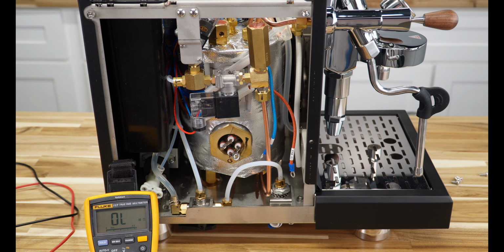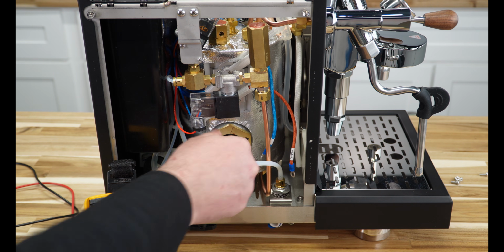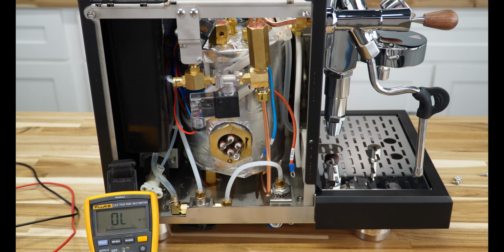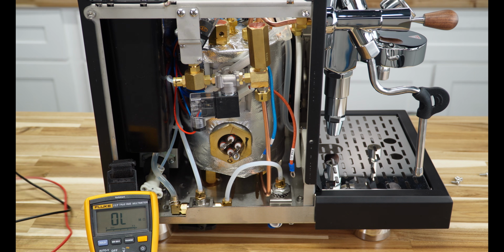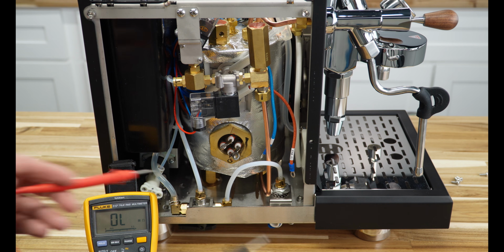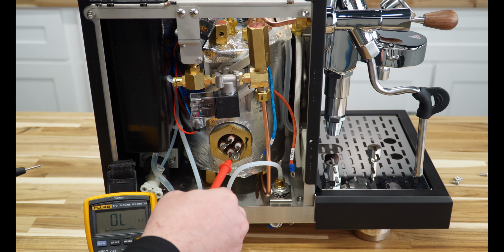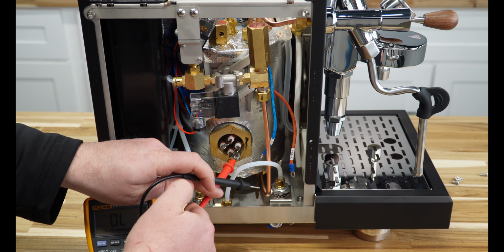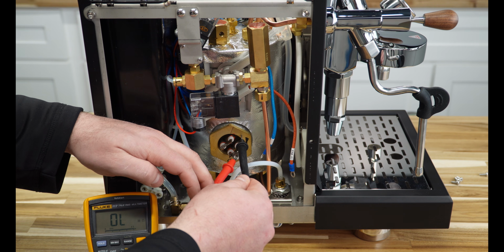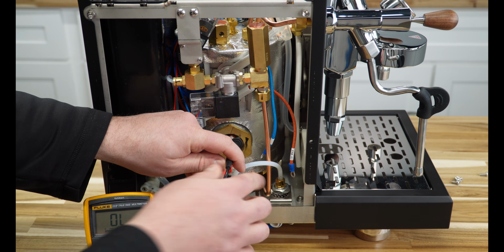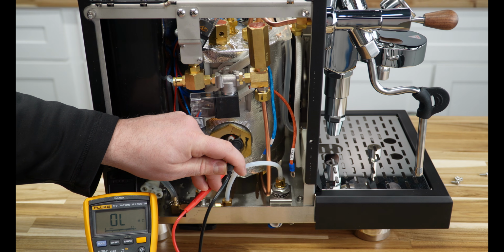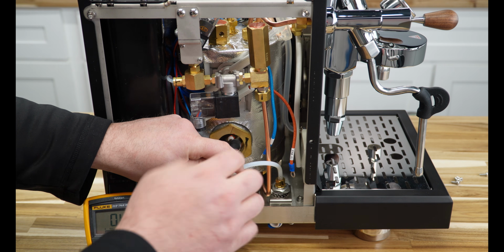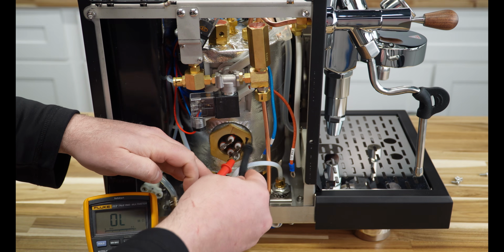While the wiring is off, the next thing I usually do is test for a pinhole issue where only one side is giving trouble. To isolate that, we check it to ground: take one probe and put it on one side of the element, then touch the other probe to the body of the machine. Here it says open, meaning there's no connection between the heating element and the frame.